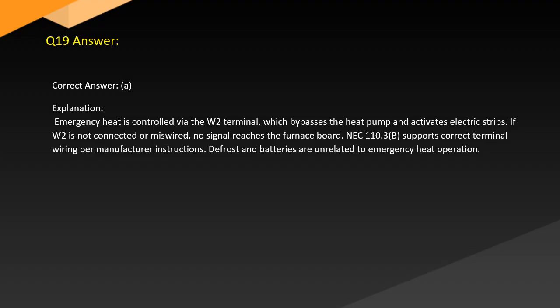Answer. Correct answer: A. Explanation. Emergency heat is controlled via the W wire, which bypasses the heat pump and activates electric strips. If it is either loose, disconnected, or miswired, no signal reaches the furnace board. NEC 110.3(B) supports correct terminal wiring per manufacturer instructions. Defrost and batteries are unrelated to emergency heat operation.